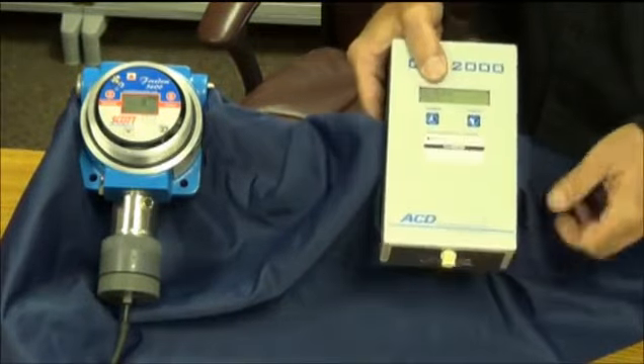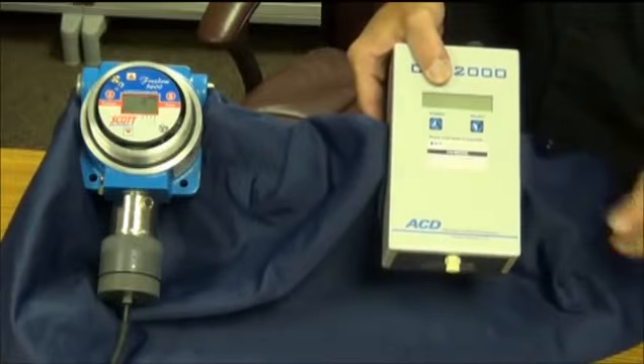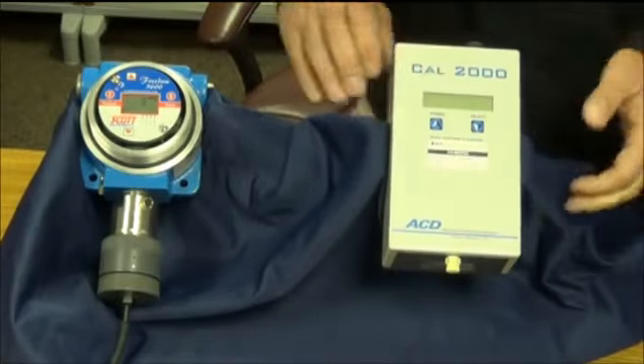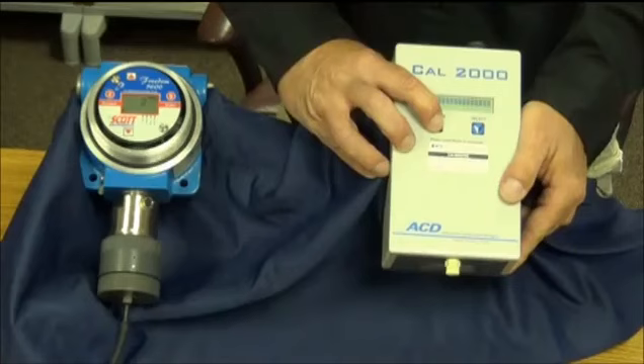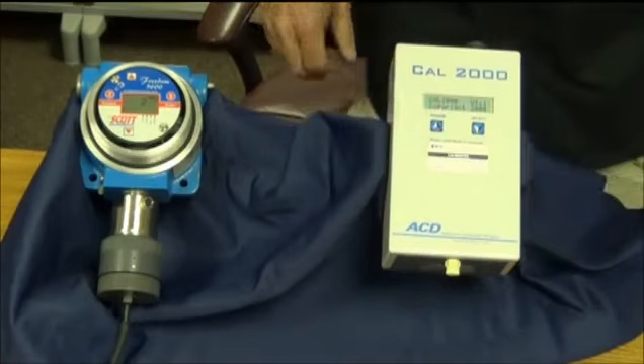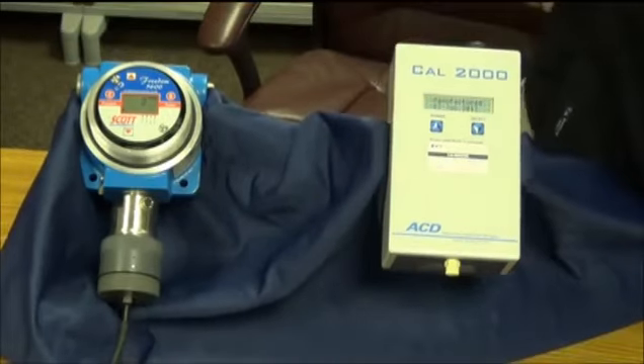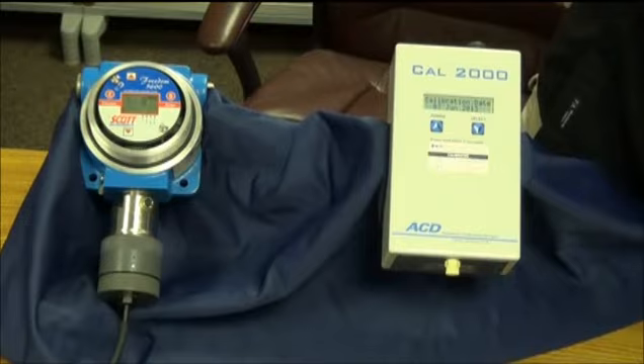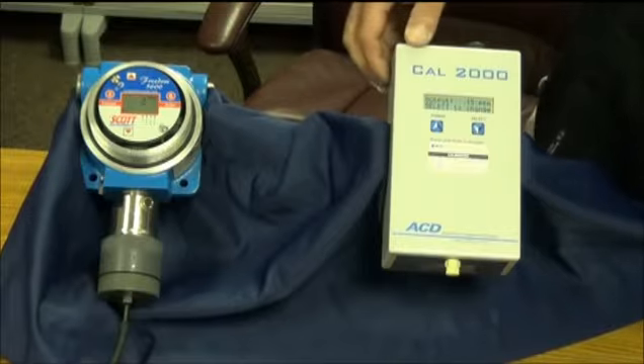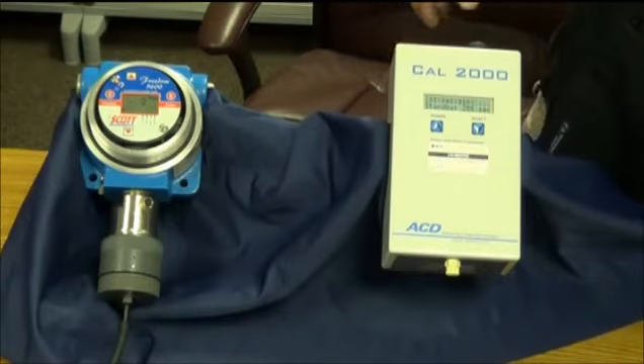I'm going to put it in this vise so that you can see the display. Normally it's going to be in your carrying case. Alright, so we're going to power the unit up. It shows you the data that the instrument has. It's got serial number, manufactured date, other data, cell life. It's 42 hours. They come with 50 hours to start with. The battery status. Quick select is a feature for H2S. Now it's set to 15 ppm and half a liter a minute.